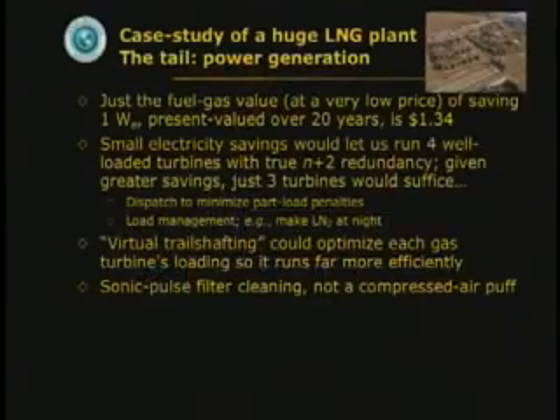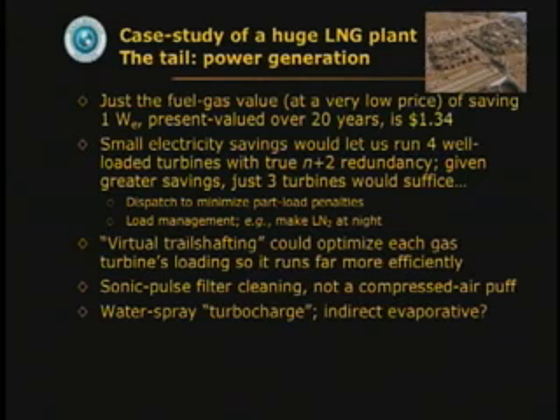We found that they were cleaning off filters with compressed air, a very, very expensive commodity, inefficiently made. We said, why don't you just put a big super woofer loudspeaker there and put a fast rise square wave pulse into it? I'll bet that puff of air blows the dust off the filter. Yes, it does. It works fine.